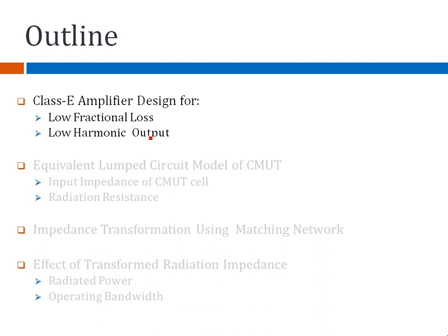And CMUTs in this study are going to be represented by a lumped circuit model, which is just a circuit model consisting of lumped circuit elements, which are representative of the distributed quantities of CMUTs, like the transduction force, membrane compliance, radiation resistance, and then you have the deflected membrane capacitance.